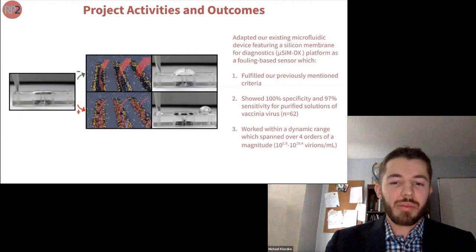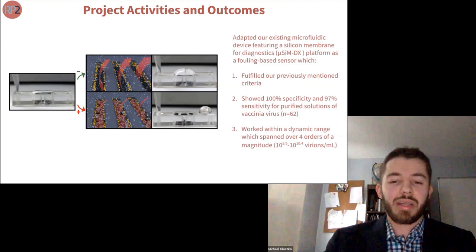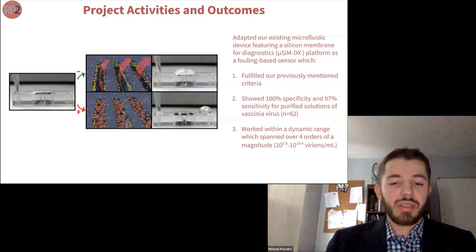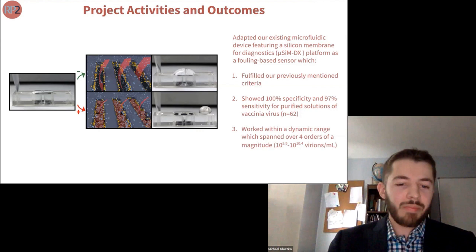With this design, we successfully produced a diagnostic by adapting one of our existing microfluidic platforms, pre-mixing purified vaccinia virus with streptavidin-conjugated antibody, and coating our one-micron slit-pore silicon membranes with biotin. We called the resulting test the Microfluidic Device Featuring a Silicon Membrane for Diagnostics, or MicroSIM DX. This test uses size and affinity-based specificity to provide 100% specificity and 97% sensitivity, within a dynamic range spanning over four orders of magnitude — roughly from 10^6 to 10^10 virions per milliliter.